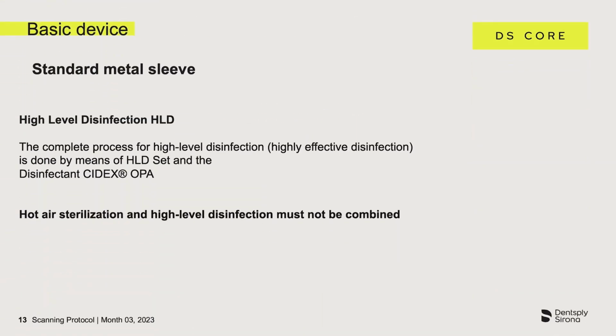First of all, pre-clean the sleeve. When handling the highly effective disinfectant, personal protective equipment must be used. The scanner sleeve has to be removed, inserted into the white protective sleeve, and then placed on the scanner holder. For highly effective disinfection, the disinfectant CIDEX OPA can be used.